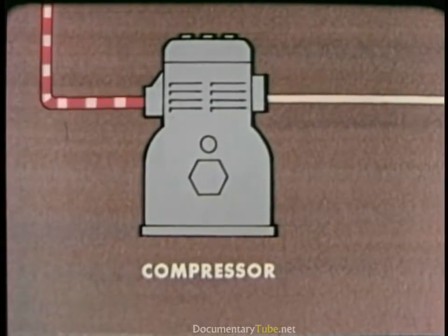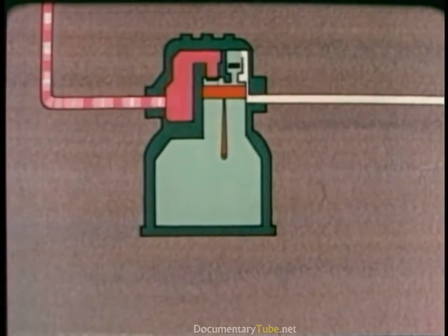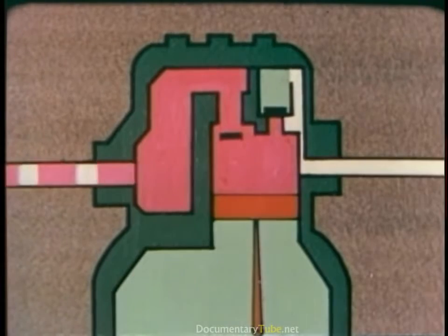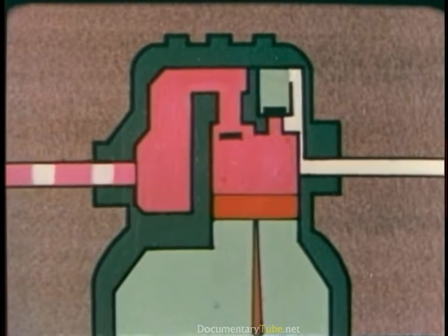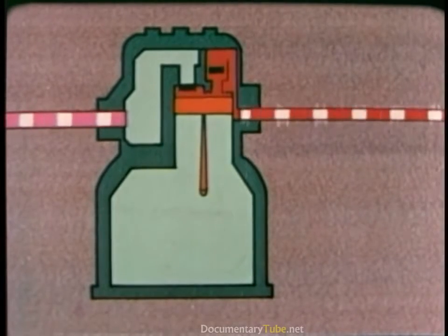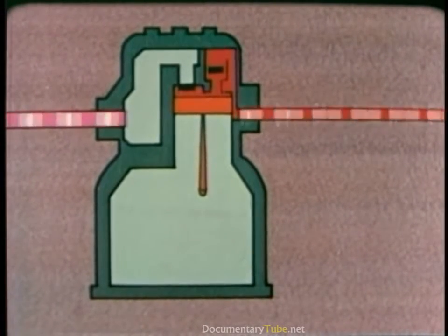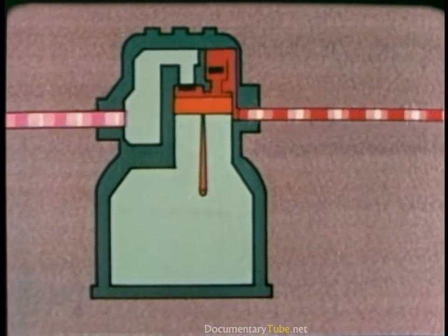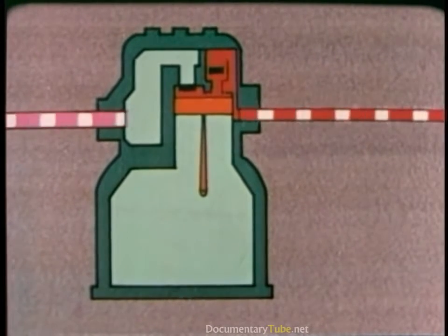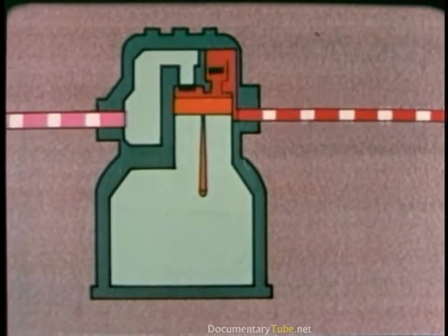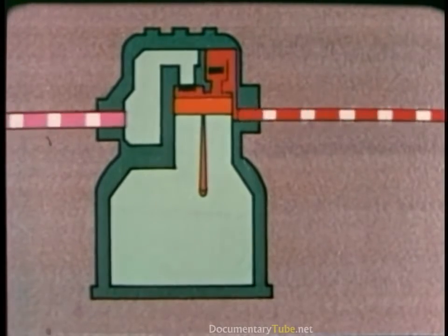The gas is sucked through the connecting line into the compressor. As the piston moves down, the suction valve opens. The gas is sucked into the compressor. As the piston starts up again, the suction valve is forced shut and the discharge valve is pushed open. On this stroke, the gas is compressed. Pressure goes up, temperature goes up. The gas, now at high pressure and high temperature, flows into the condenser.